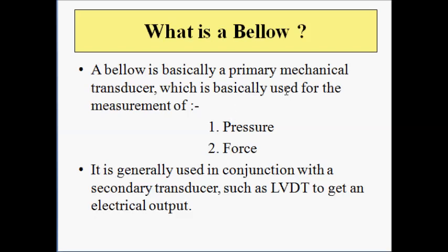Primary transducer means that it converts pressure or force into suitable mechanical motion or displacement. Generally it is used in conjunction with a secondary transducer such as LVDT so that we can get an electrical output in terms of voltage or current. So basically a bellow is a primary transducer used for measurement of pressure and is generally used in conjunction with a secondary transducer.